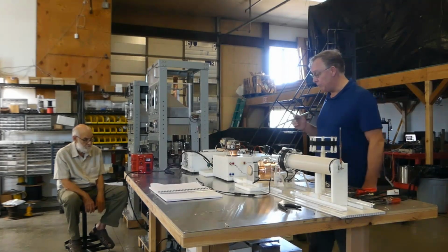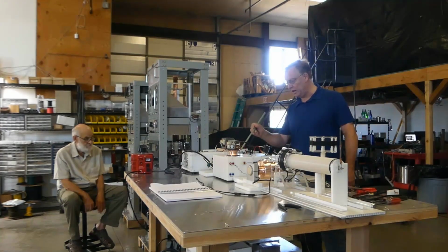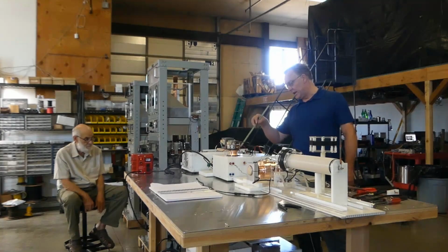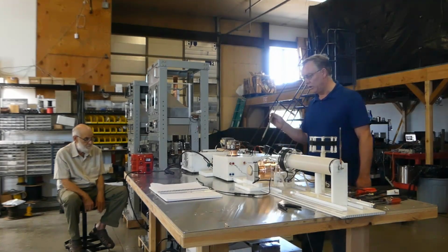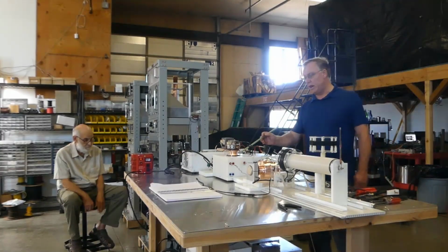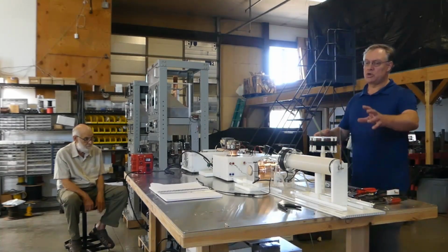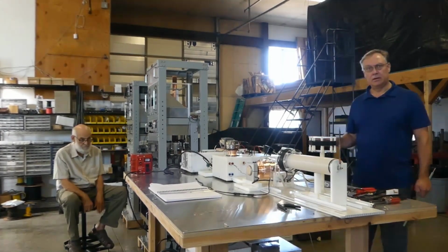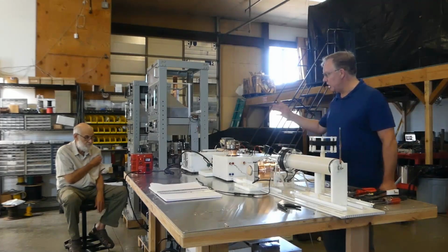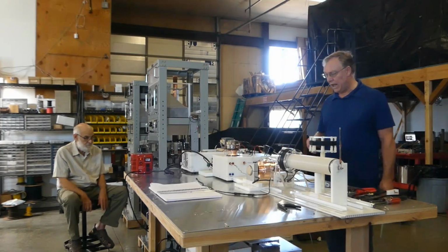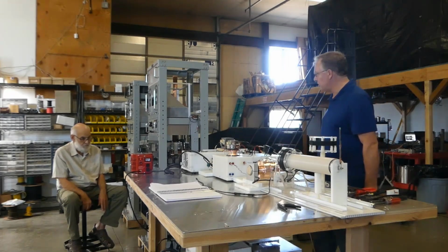We noticed that because the fan, which does the cooling here, is connected to a small DC switch mode power supply, which is located not that far from the anode. The anode is buried down inside this box here. When we turned it on and couldn't strike the arc, the fan stopped. When we turned off the high voltage, the fan started again. So that was rather strange. Eric, do you want to go into more detail about why that is?